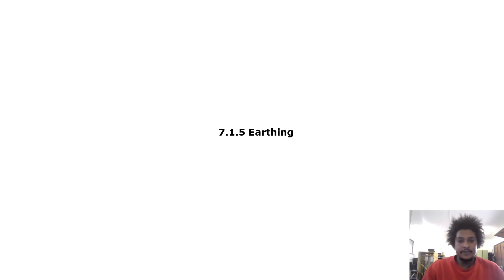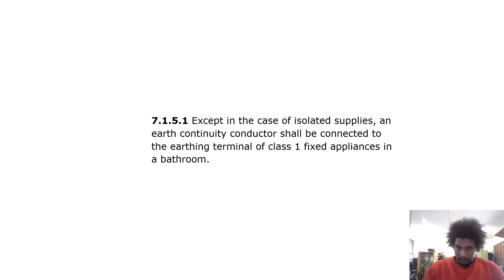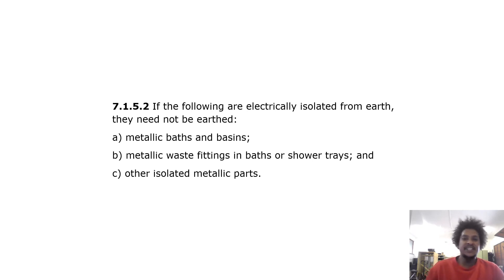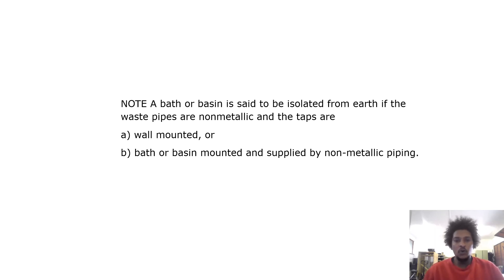Earthing: except in the case of isolated supplies, an earth continuity conductor shall be connected to the earthing terminals of Class 1 fixed appliances in a bathroom. If the following are electrically isolated from earth, they need not be earthed: metallic baths and basins, metallic waste fittings in baths or shower trays, and other isolated metallic parts. Note: a bath or basin is said to be isolated from earth if the waste pipes are non-metallic and the taps are wall-mounted or bath/basin-mounted and supplied by non-metallic piping.